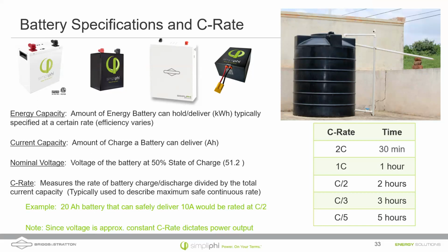Thank you, Nathan. Let's look at the example at the bottom when we're talking about C rate. I want to make sure everybody understands C rate, because a lot of our competitors' batteries are typically rated at C/3, which means they could charge or discharge in 3 hours. Ours can do it a little bit faster, in 2 hours, but it's important to make sure that you don't exceed this rate, especially continuously, right? Now, our batteries are capable of surging, but they can't surge continuously for a full discharge cycle.